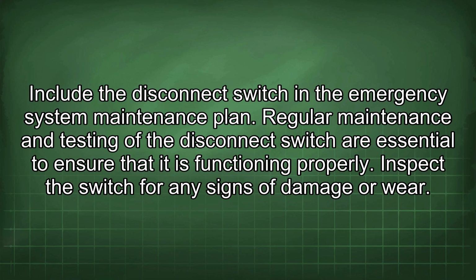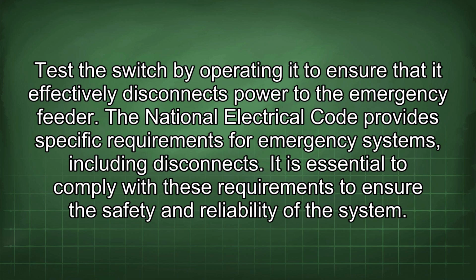Regular maintenance and testing of the disconnect switch are essential to ensure that it is functioning properly. Inspect the switch for any signs of damage or wear. Test the switch by operating it to ensure that it effectively disconnects power to the emergency feeder. The National Electrical Code provides specific requirements for emergency systems, including disconnects. It is essential to comply with these requirements to ensure the safety and reliability of the system.